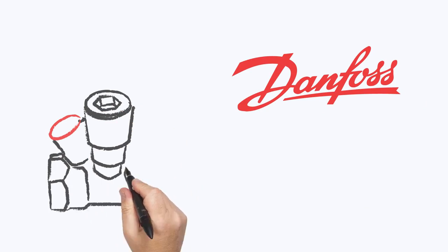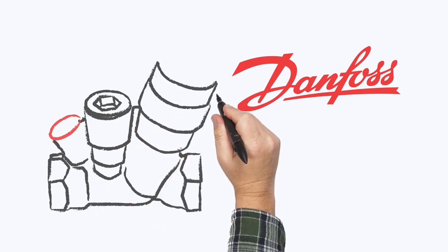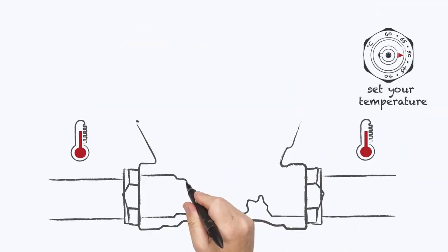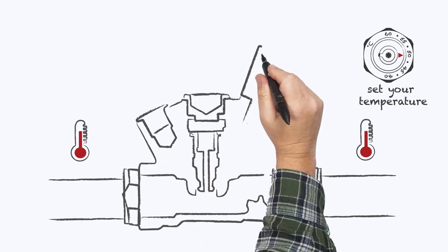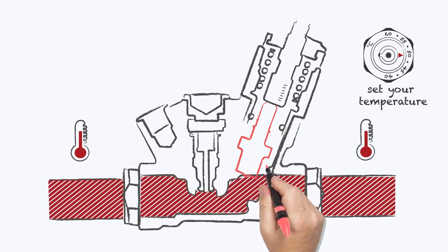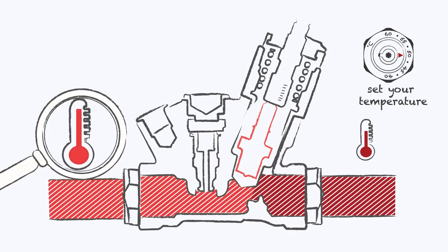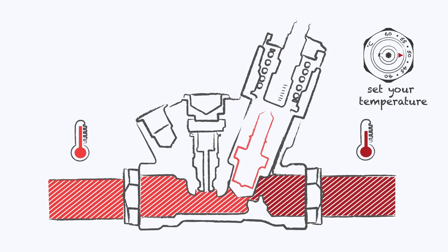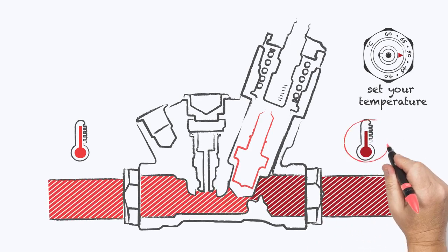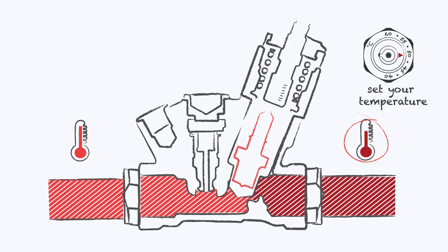Innovative Danfoss now offers a solution for these problems. MTCV for thermal balancing. The multifunctional thermostatic circulation valve has been specifically designed for your benefit. Inside the valve, a thermoelement quickly reacts to temperature changes of the water by closing or opening the valve. This is how the MTCV secures a constant water temperature, regardless of the dynamics of the system.